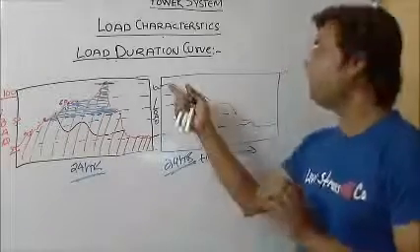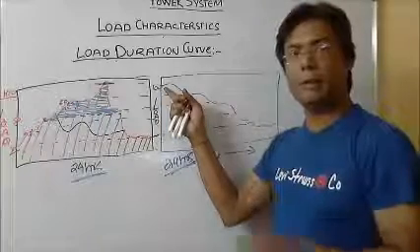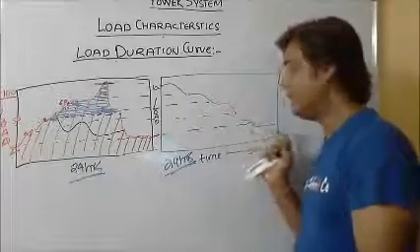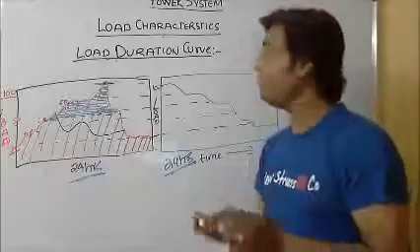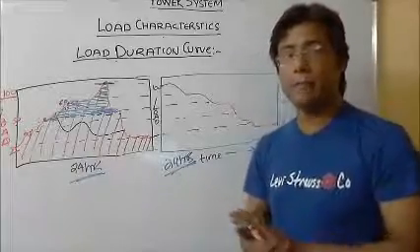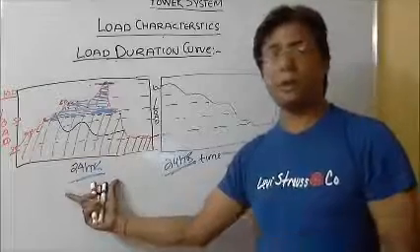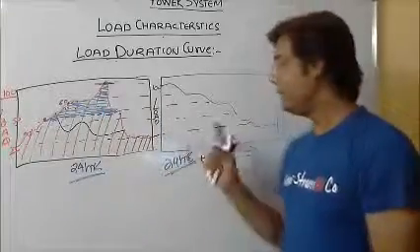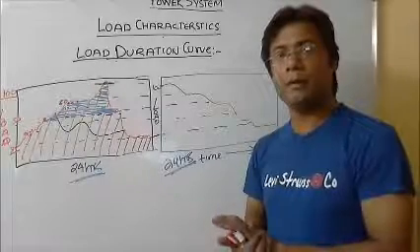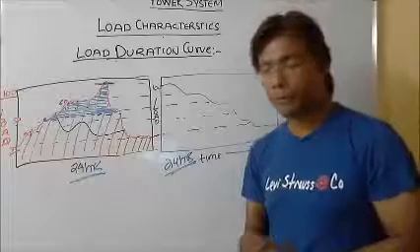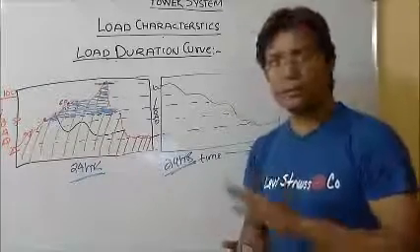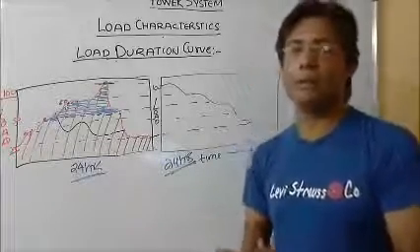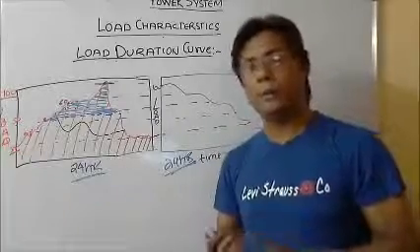I have the maximum demand first at 100, then less demand, then less and less down to the minimum demand. So the load duration curve and load curve are one and the same thing. The only difference is that the load curve is in chronological order showing what is actually happening in the system, while the load duration curve gives the load arranged from maximum to minimum. The area under both the load duration curve and load curve is always the same.